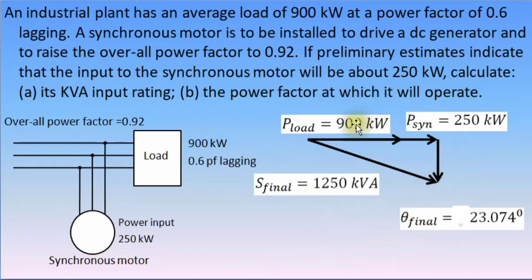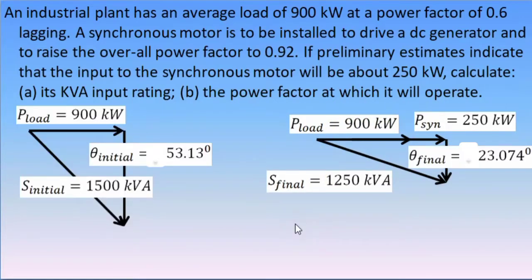So this is the Phasor diagram when the synchronous motor is being installed. Comparing both conditions, the power factor has been improved. And also, the apparent power needed for the final condition is lower compared to when the synchronous motor is not yet installed at the initial condition. 1,500 kVA minus 1,250 kVA, that is 250 kVA. The 250 kVA reduction in the apparent power is a considerable value. That's why in industries and other facilities, power factor correction is employed.